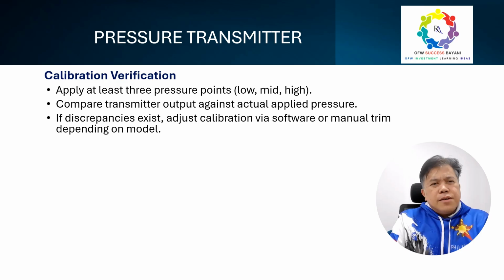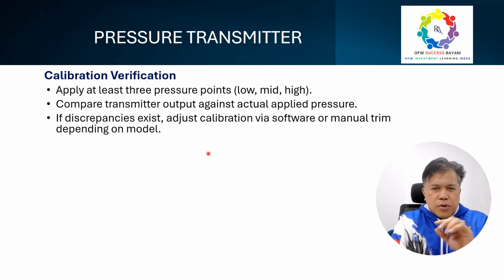So pressure transmitter calibration is required. That's mandatory. Calibration verification is mandatory. Apply at least three pressure points: low, medium and high. Compare the transmitter output against the actual applied pressure. If a discrepancy exists, of course you need to redo it and then check the software, or do a manual trim, depending on the model. Depends. We have different types of calibration tests in different companies, with different calibration benches and different testing materials and equipment.